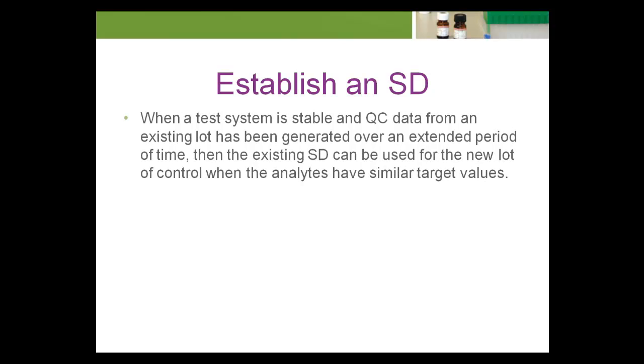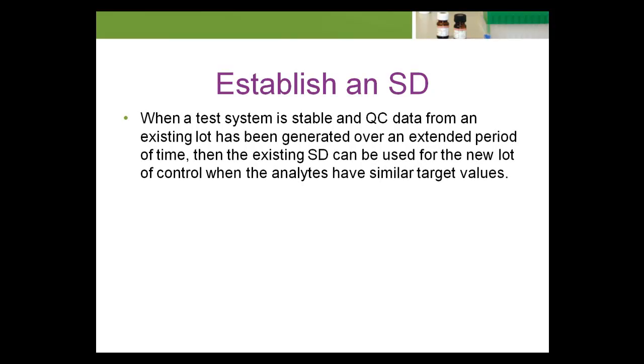When a test system is stable and QC data from an existing lot has been generated over an extended period of time, then the existing SD can be used for the new lot of control when the analytes have similar target values.